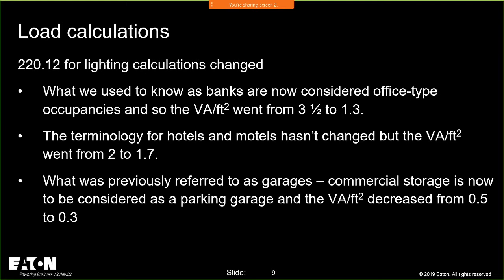So if you look at 220.12, we did a couple of things. So number one, we adjusted the VA per square foot, but what we recognized was that the occupancy types that are in 220.12 didn't correlate with what ASHRAE and the energy codes were using. They were correlated with each other, but what we called banks, there was nothing in ASHRAE, for example, that said that a bank is an occupancy type. And when you looked at all the data that they would be using for watts per square foot determinations, it was critical that we line up the terminology in 220.12 with the terminology in ASHRAE.